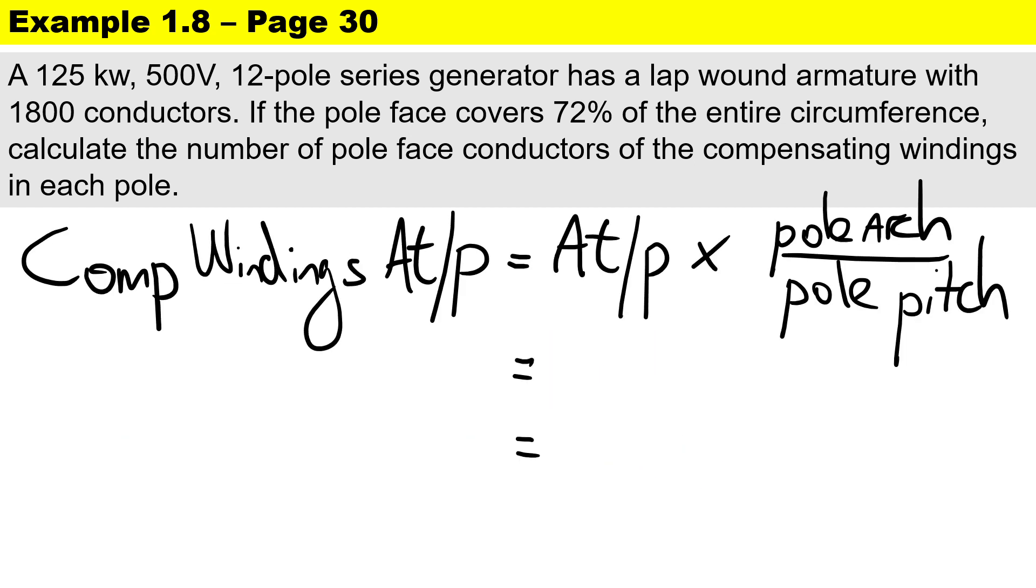Next, to calculate the compensating winding ampere turns per pole: it's the armature ampere turns per pole multiplied by the pole arc and pole pitch ratio. We already calculated the armature ampere turns per pole as 1562.5, multiplied by the ratio of 0.72 because it covers 72% of the circumference of the pole face. The answer is 1125 ampere turns per pole.